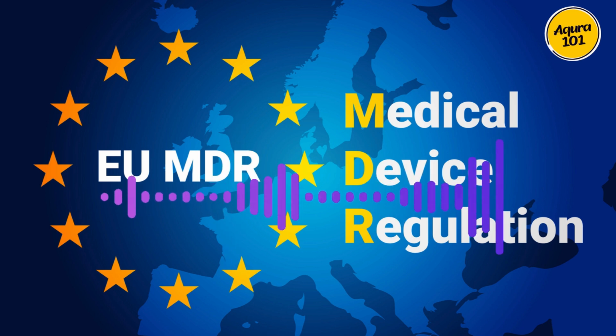Precisely, the person or company assembling these systems or packs has specific obligations under the MDR. They need to follow certain procedures to verify that the assembled system is safe and effective for its intended use. This might involve reviewing the documentation for the individual components, conducting tests on the assembled system, or doing a risk assessment to identify any potential hazards that might arise from combining the devices in a particular way. It makes sense. You wouldn't want a situation where a surgical kit, for example, is put together in a way that makes it more likely for a surgeon to accidentally grab the wrong instrument or for a component to become dislodged during a procedure. Exactly.